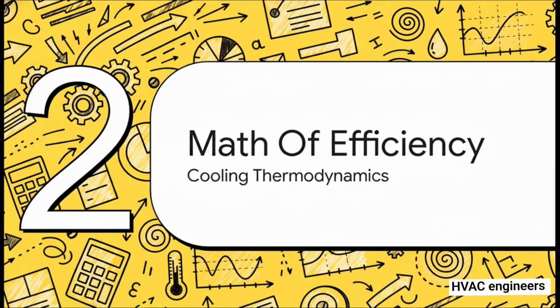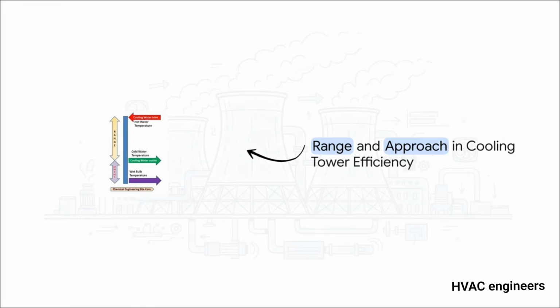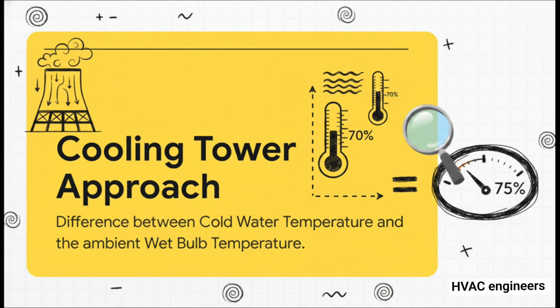Moving right along to part two, the math of efficiency. When we talk about cooling tower thermodynamics, range and approach are the two absolute key concepts you need to know. Range is simply the temperature drop, the difference between the hot water coming into the tower and the cold water leaving it. The approach is the gap between that cold water output and the ambient wet bulb temperature of the outside air. To put it simply, the approach is your ultimate indicator of performance.